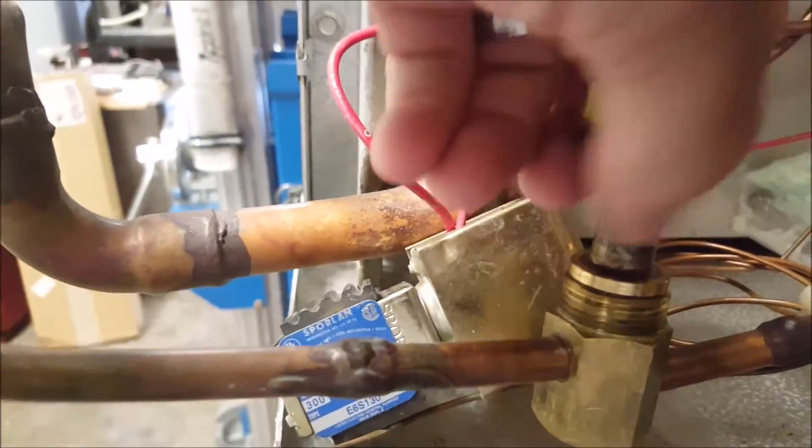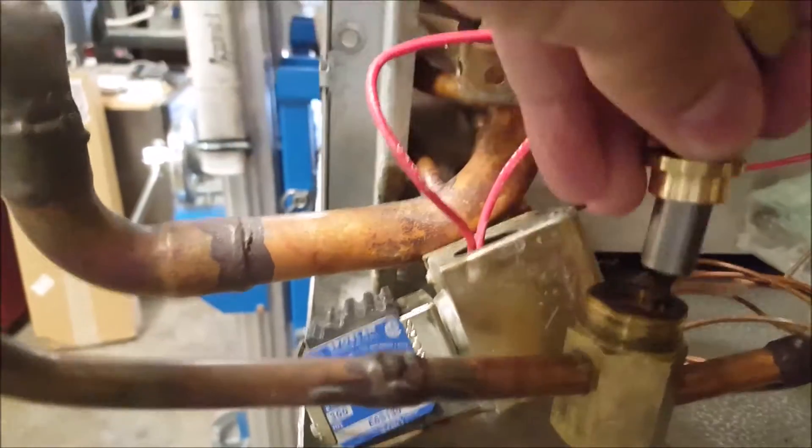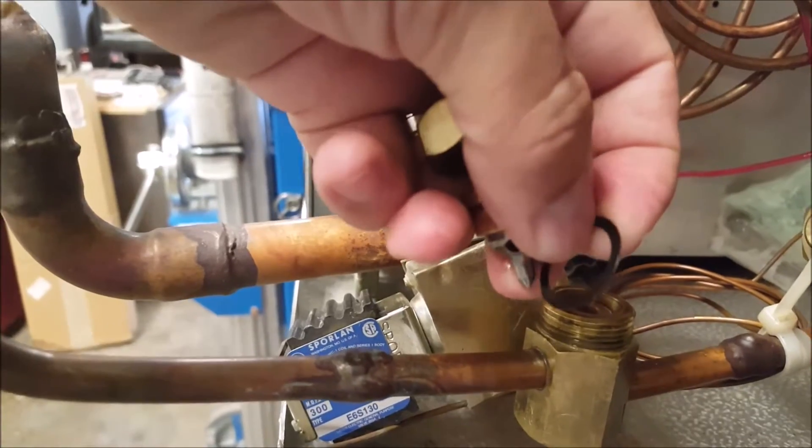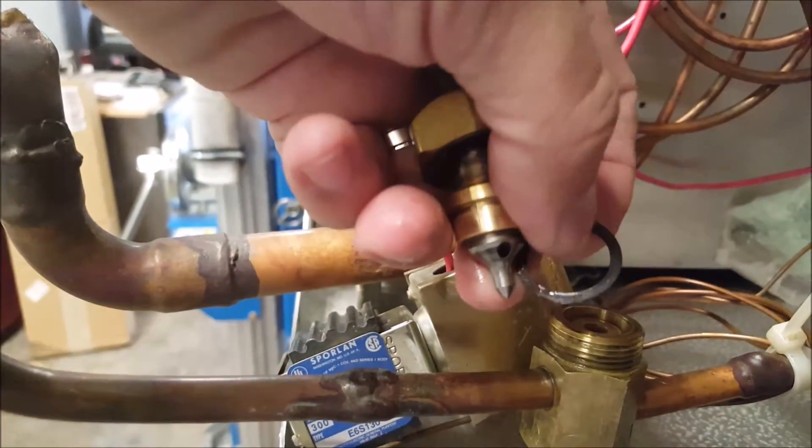When you're going to solder this in place, the best thing to do is just take this thing apart. Take your nut off of there and pull your stem out of here and all your guts. Just don't lose it all. There's a gasket that you could potentially melt if you were to solder it with this thing still in it.